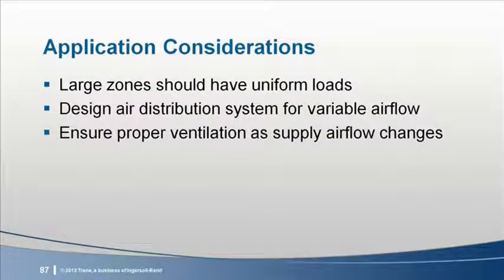Likewise, if a zone has some type of minimum exhaust requirement, like a restroom, kitchen, or locker room, demand control should not be allowed to reduce the intake airflow any lower than the required exhaust, unless the zone receives makeup air from some other source. The next consideration is related to system operation during heating. ASHRAE 90.1 addresses single-zone VAV during cooling operation.